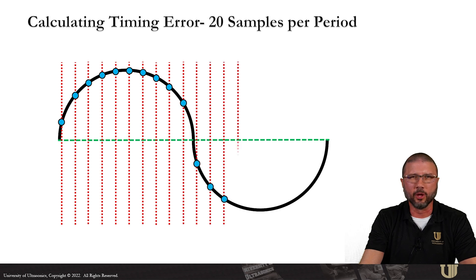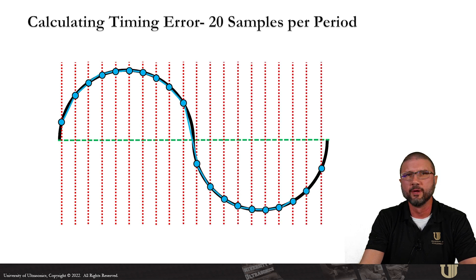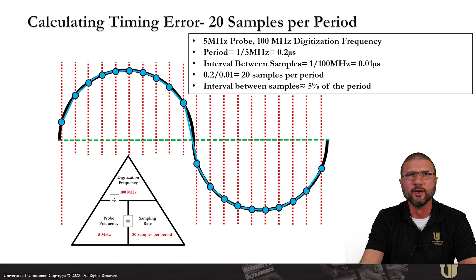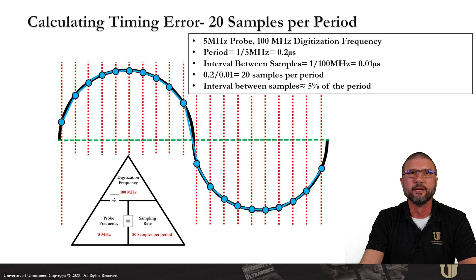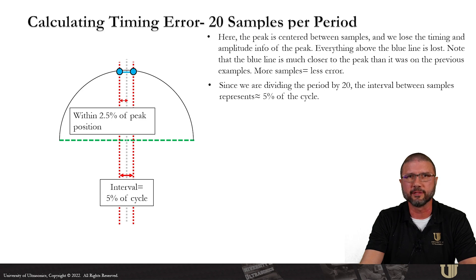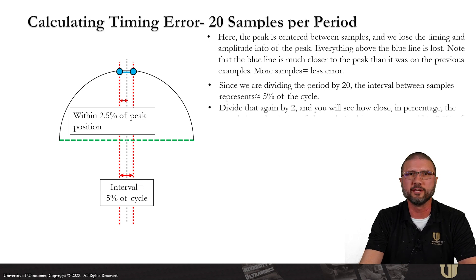For the next scenario, we're going to blow it out of the water — a 5 megahertz probe with a 100 megahertz digitizing frequency, giving us 20 samples per period. By the way, 100 megahertz is the default digitization frequency in many of today's phased array instruments, before any compression, sub-sampling, or points quantity adjustments. The more samples you collect, the closer you get to the peak, and the better your timing and amplitude fidelities are going to be. Here we show the peak centered between samples and we lose anything above that blue line, but notice the blue line is much closer to the peak than previous examples.